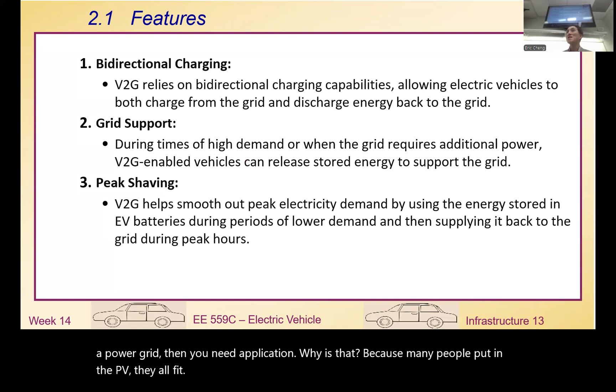Why is that? Because many people put in PV and they all feed their current back to the power grid. During the day that will be too much, which makes the voltage not stable. If everybody does the same thing during the day, the voltage may rise, which we don't want.